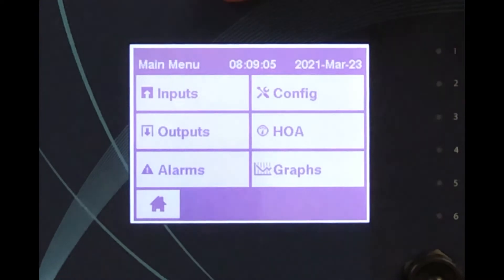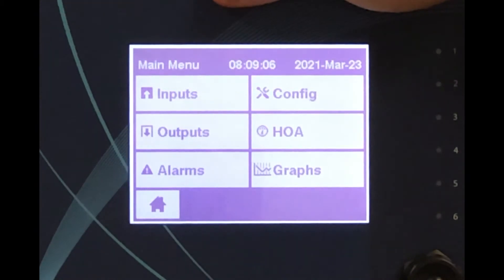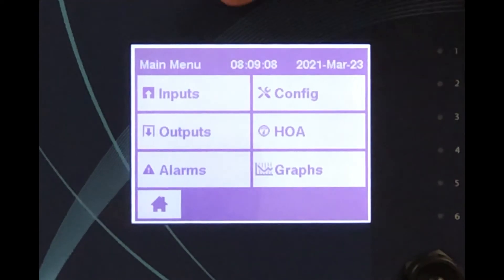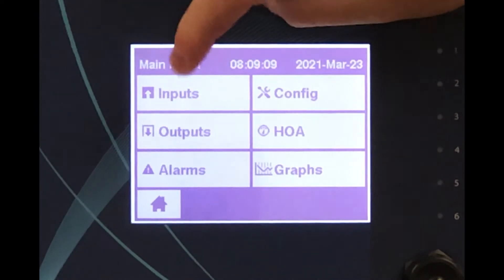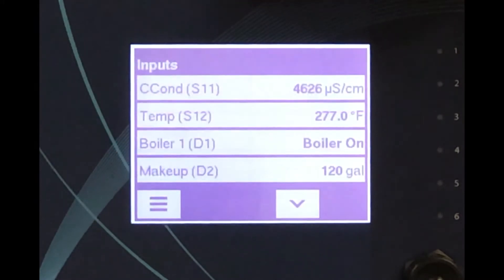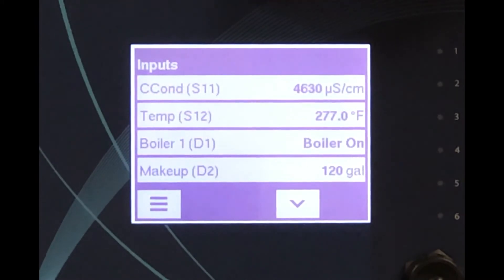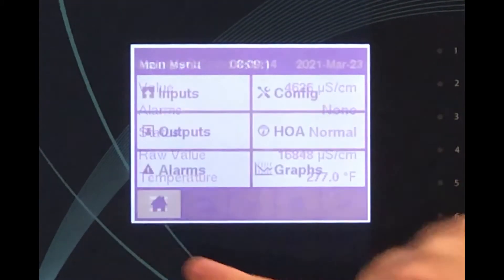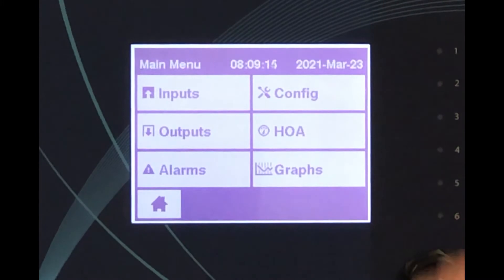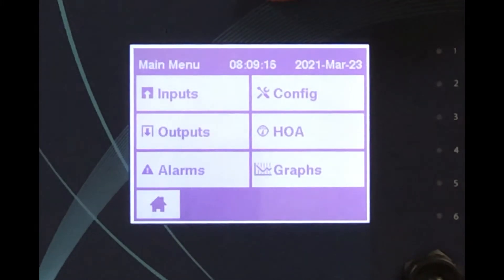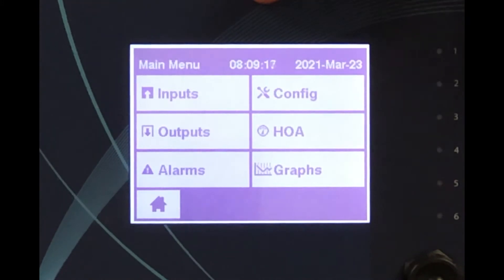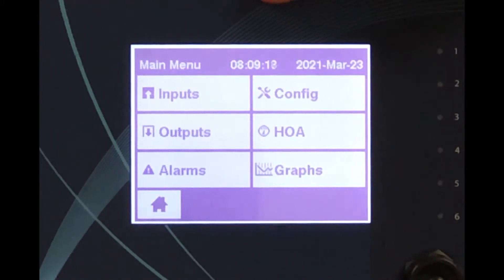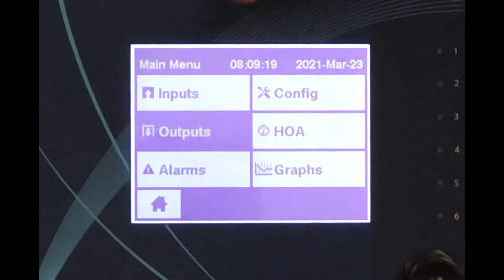All programming and calibration for the conductivity measurement is done in the inputs menu, while programming for the blowdown valve relay that will control the conductivity in the boiler is in the outputs menu.